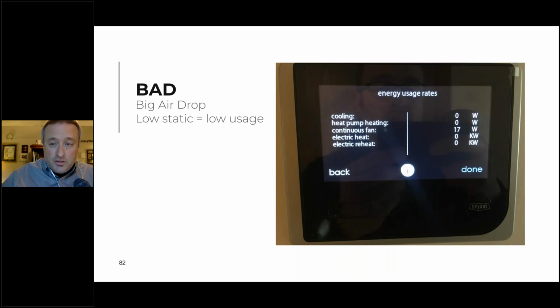The magic of this—this is the piece of equipment we like using a lot. Note how much juice it's using: 17 watts. If you look at an ERV fan, they usually use somewhere between 15 and 40 watts each, and there's two of them. This is the air handler, the main system. On low, it's pulling 17 watts, and I have yet to see one over 40, even on the 4-ton units.